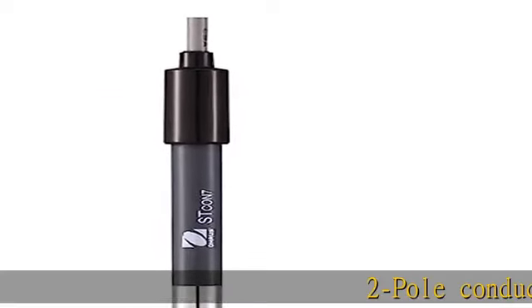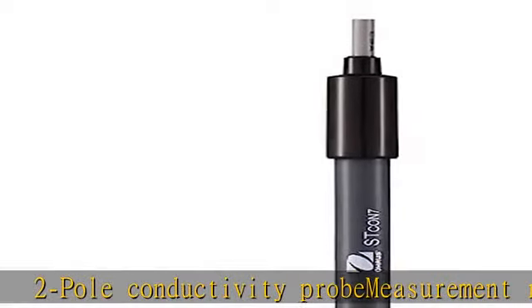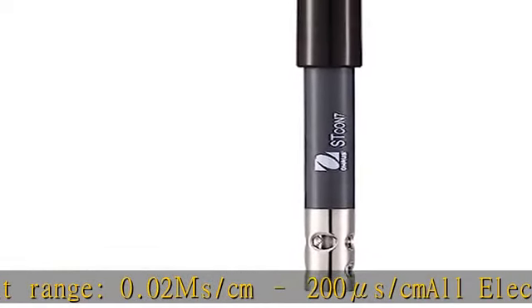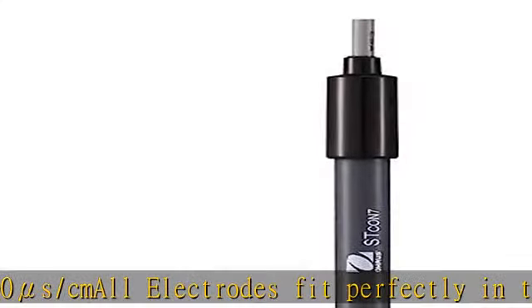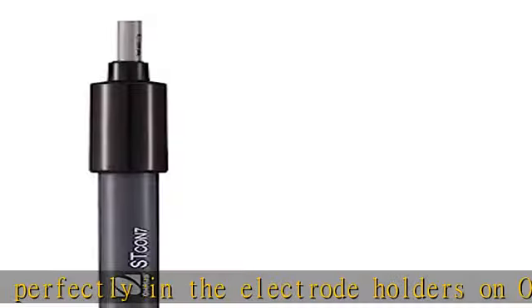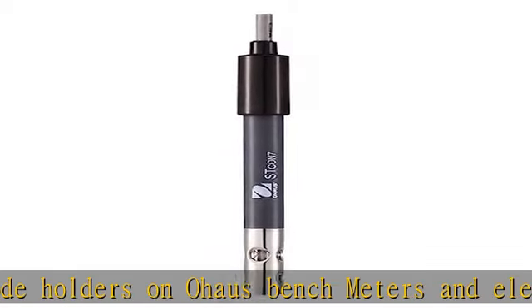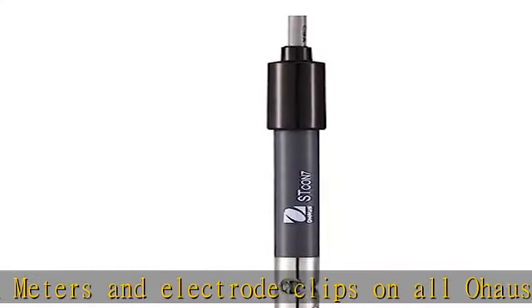2-pole conductivity probe, measurement range 0.02 µs/cm to 200 µs/cm. All electrodes fit perfectly in the electrode holders on Ohaus bench meters and electrode clips on all Ohaus portable meters. Check the description to get this product today at the best price.